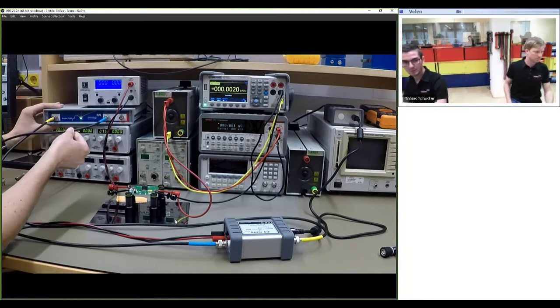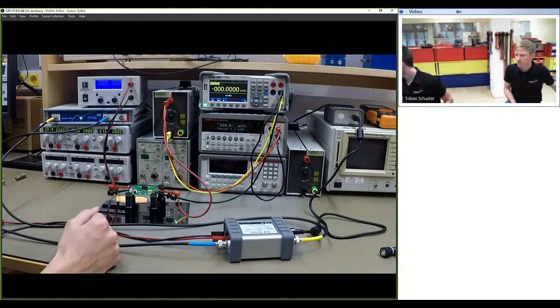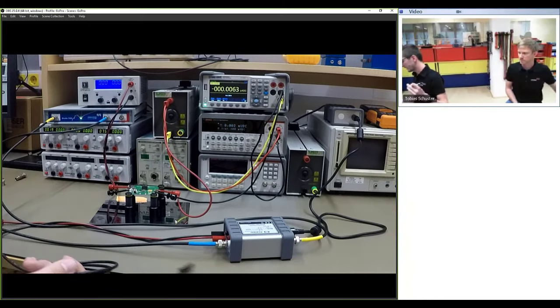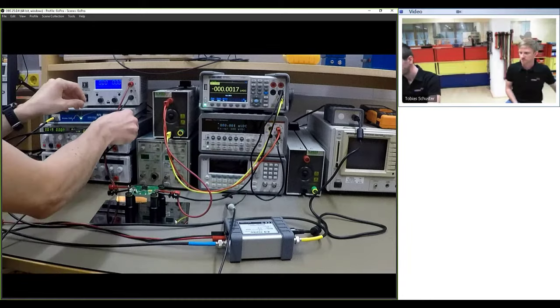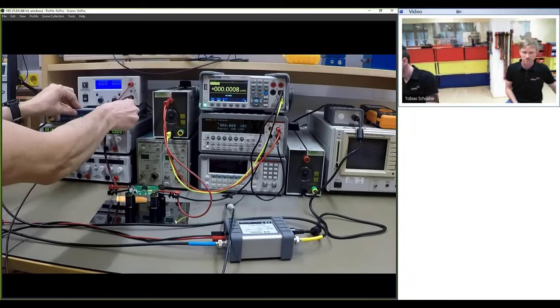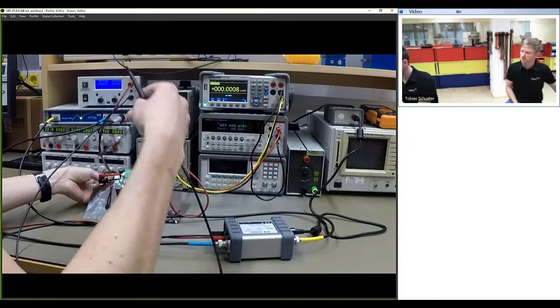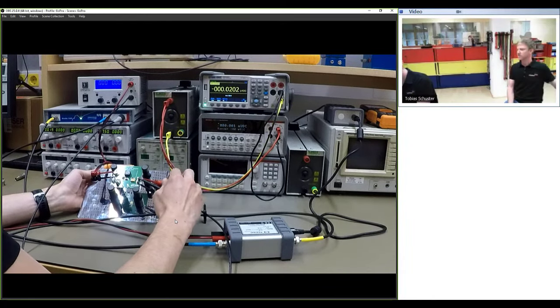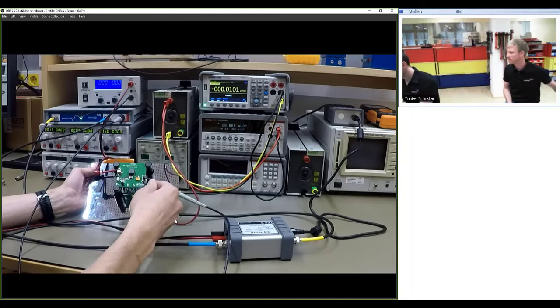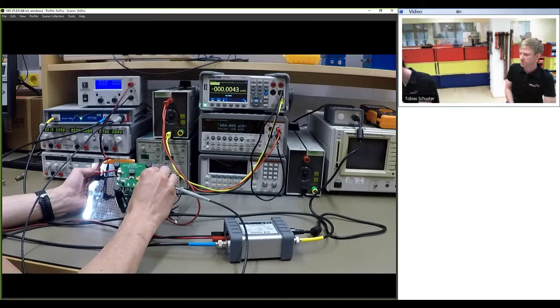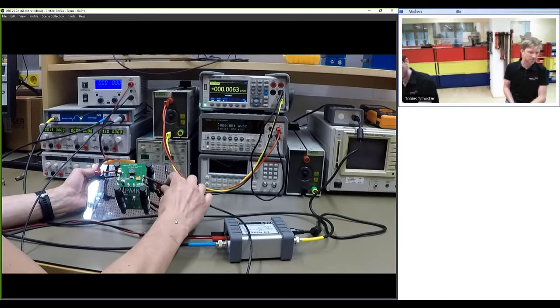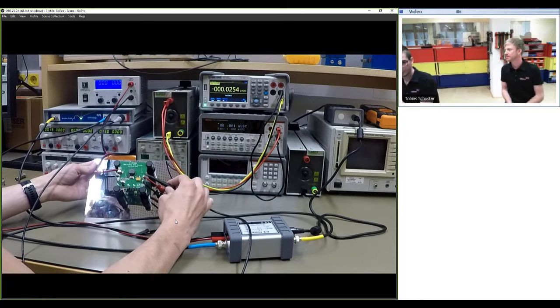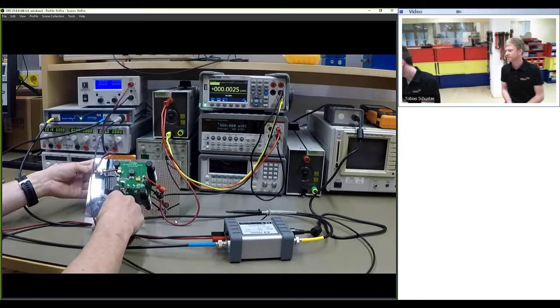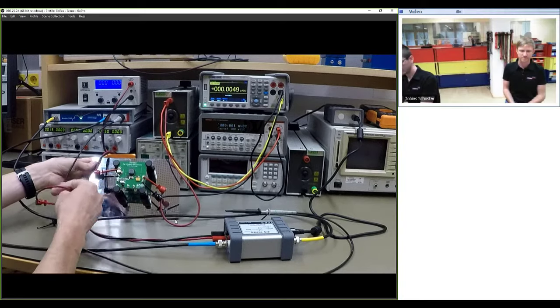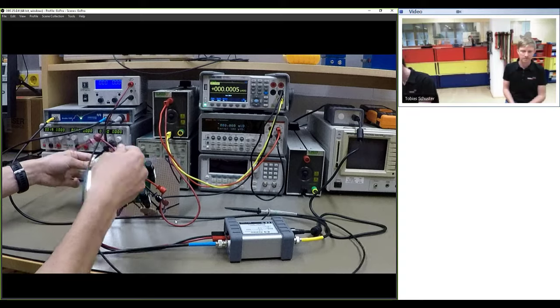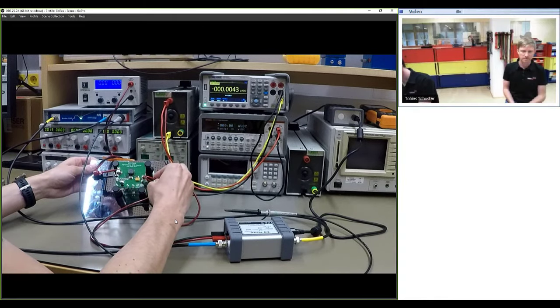And on channel 2 of the Bode 100, we now have to connect a voltage probe, which is connected to the output of our device under test. In this case we use a 10-to-1 probe. We could still use a 1-to-1 since it's below 50 volts, but we use the PML 10-to-1 probe. It just provides better protection to the inputs, and we don't want to break stuff during the webinar. Before I put on the probe, I will connect the current injector to the output of the voltage regulator, so it's easier for the connection.